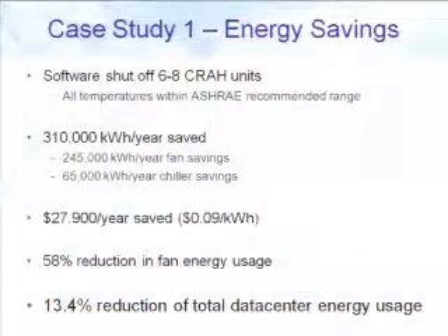And then for the other 8 units, we turn them on and off because they only had 1 speed, as well as adjusting their set points to adjust their chilled water valve position. So what was interesting is at any given time, typically 6 to 8 of the units were turned off by our system. And which ones were turned off depended on the conditions of the servers, while, of course, maintaining all the temperatures within ASHRAE limits.